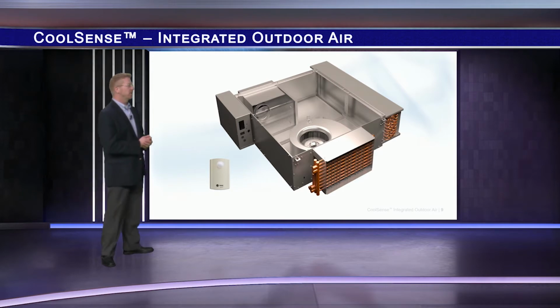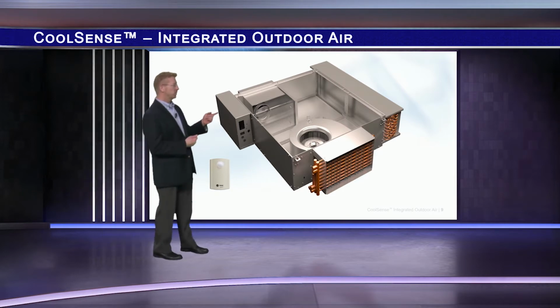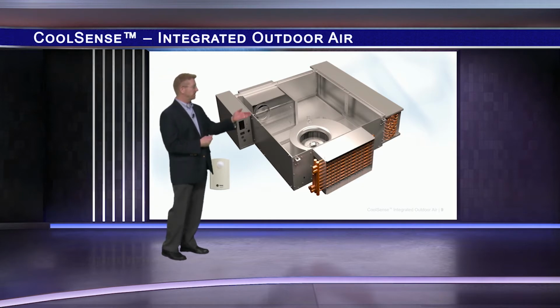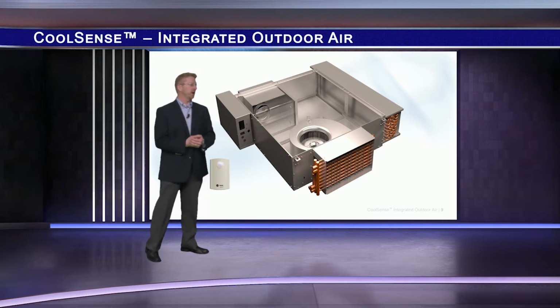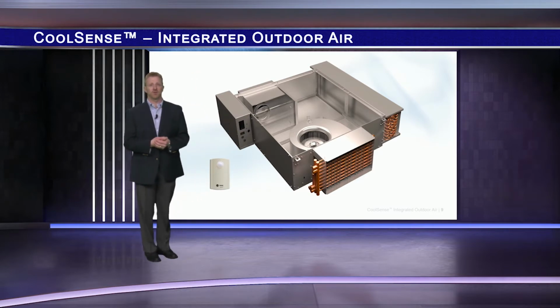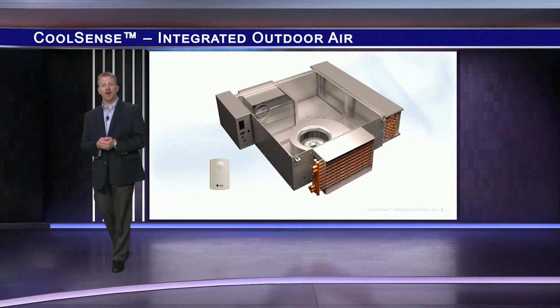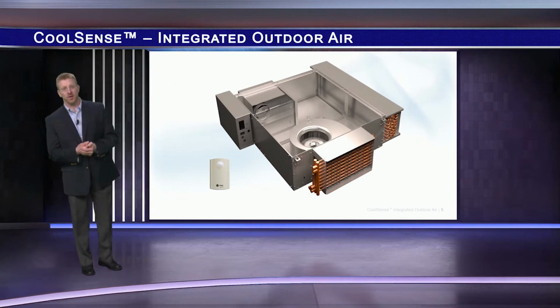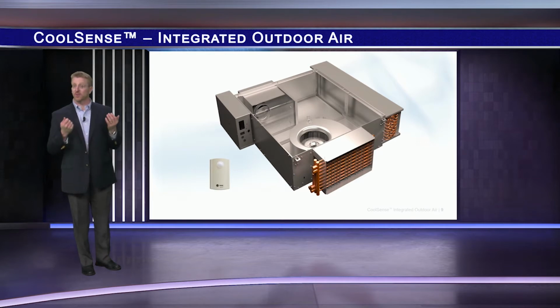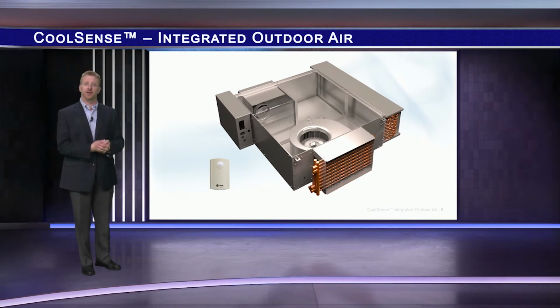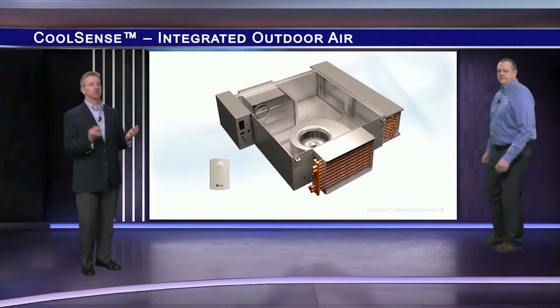Inside the box, the conditioned air mixes with recirculated air from the zone that passes through the sensible cooling coil to the variable speed fan, supplying the air into the downstream ductwork and diffusers. The CoolSense terminal units can also be equipped with hot water coil or electric heat. This offers flexibility in your system design based on climate and building use. This is a fairly simple device made with familiar parts that we've used for many years in more conventional systems.